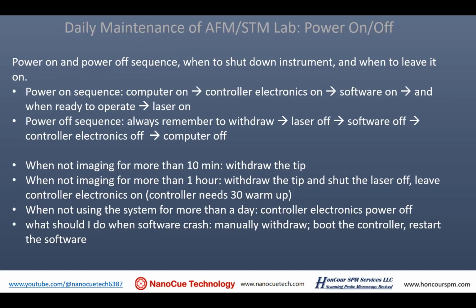And again, I'm not going to read it line by line, and you can always go to YouTube and freeze the frame and read through them. How do you want to keep your laser or machine on and off? I would say when you're not imaging for 10 minutes, you should withdraw the tip, because when you're not withdrawing, the high voltage is on. And when the high voltage is on for a long time without scanning, it will gradually, slowly depolarize your scanner. So if you're not scanning, withdraw.